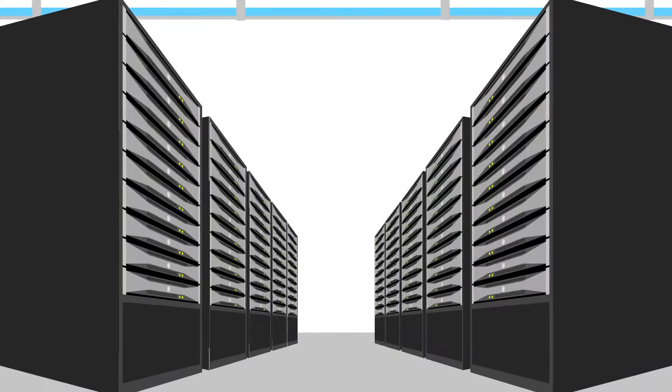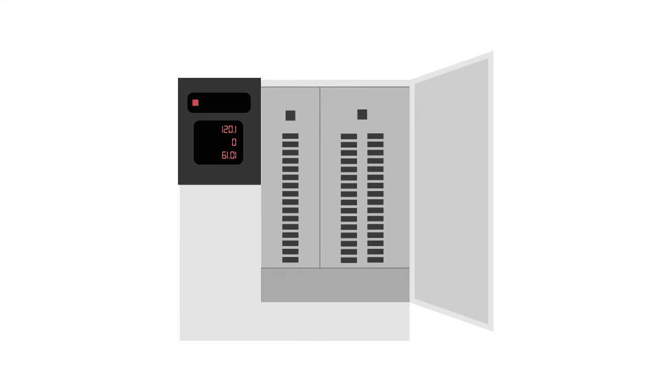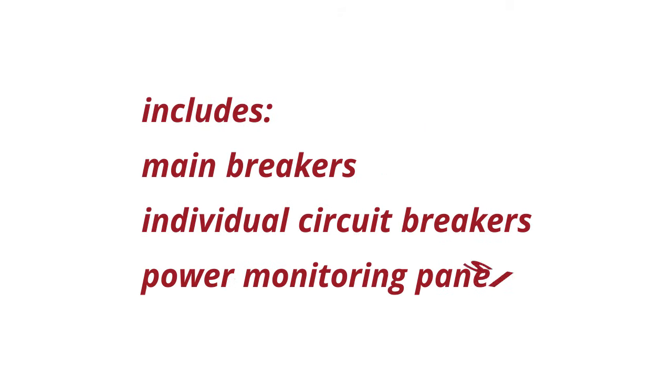Sometimes for more power-hungry applications like multiple server cabinets, a larger PDU solution is necessary, like a cabinet PDU. Standalone cabinet PDUs are self-contained units that include main breakers, individual circuit breakers, and power monitoring panels. The cabinet also provides for grounding via internal bus bars.